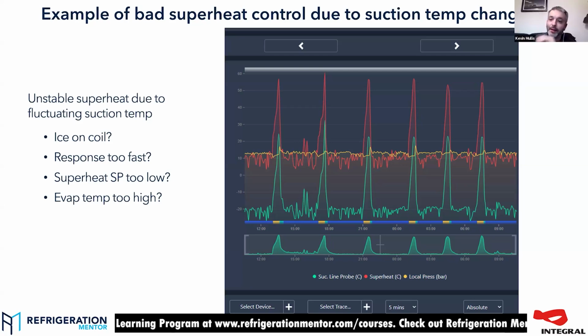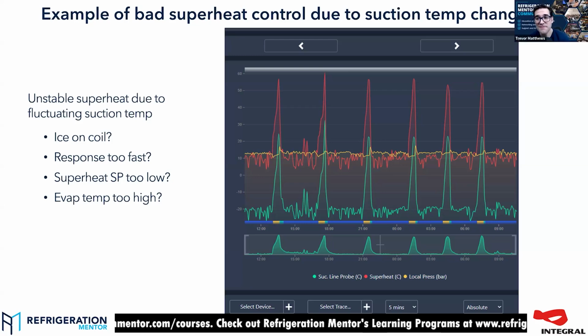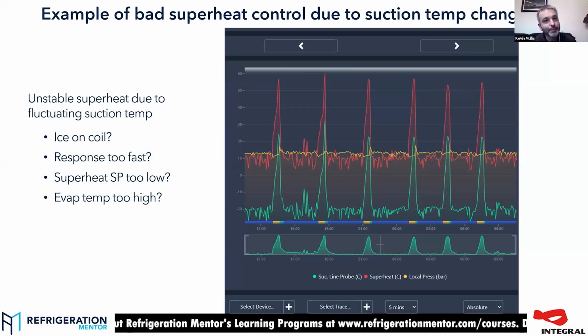Yeah, absolutely. And I think Chris probably said, and certainly RDM in their documentation says, if you use what I think is called EET mode on an RDM controller, that comes with a health warning. If you do it that way and you've got an iced up coil, as we said before, it won't care. If the temperature's high because you've blocked the discharge air and you are sending a ton of liquid through that coil, it's not going to care because it's looking at the temperature. So use it with caution if you use that facility. There is a reason why it comes defaulted to superheat control.